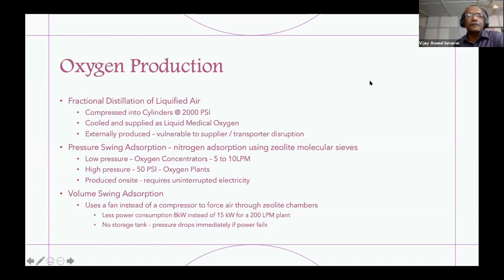There are only two common ways of producing oxygen. The first is fractional distillation of liquefied air. You liquefy air at something like minus 200 degrees centigrade, and as you slowly warm it to minus 183, oxygen starts boiling and becomes gas. That is cooled and supplied as liquid oxygen, or it is compressed into cylinders at 2000 psi and supplied as cylinders. The problem with this is that it is vulnerable to external disruption—if the supplier doesn't have enough oxygen, or the transporter has a problem, or the road is bad, then you don't get your oxygen.